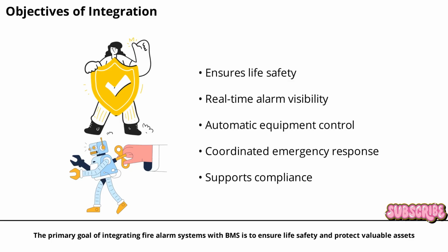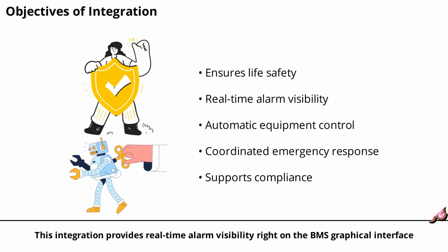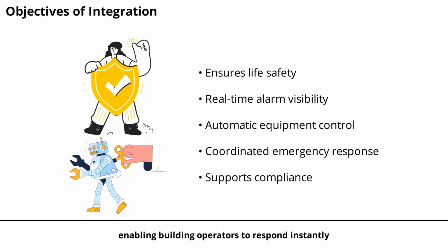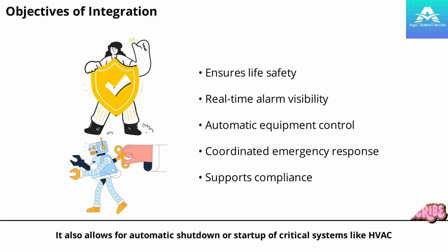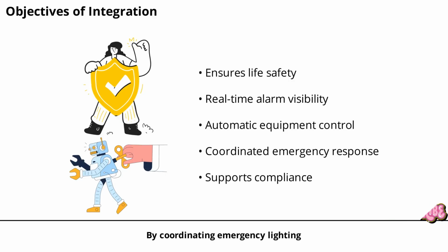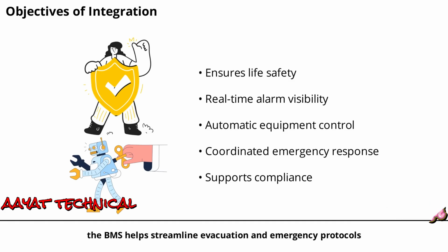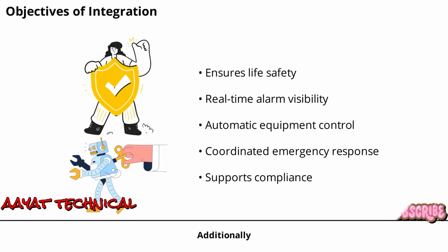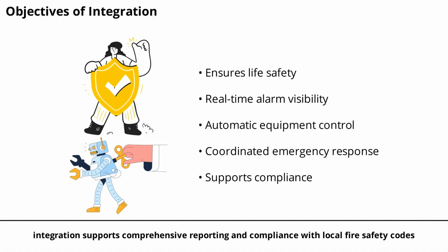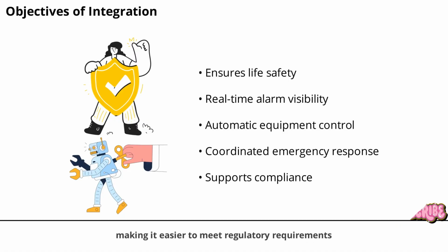The primary goal of integrating fire alarm systems with BMS is to ensure life safety and protect valuable assets. This integration provides real-time alarm visibility right on the BMS graphical interface, enabling building operators to respond instantly. It also allows for automatic shutdown or startup of critical systems like HVAC, lifts, and dampers during emergencies. By coordinating emergency lighting, access control, and even CCTV responses, the BMS helps streamline evacuation and emergency protocols. Additionally, integration supports comprehensive reporting and compliance with local fire safety codes, making it easier to meet regulatory requirements.